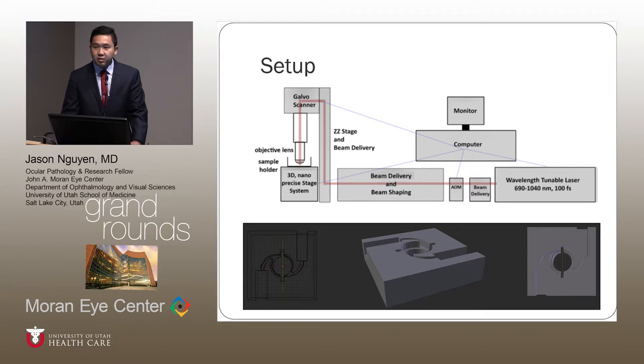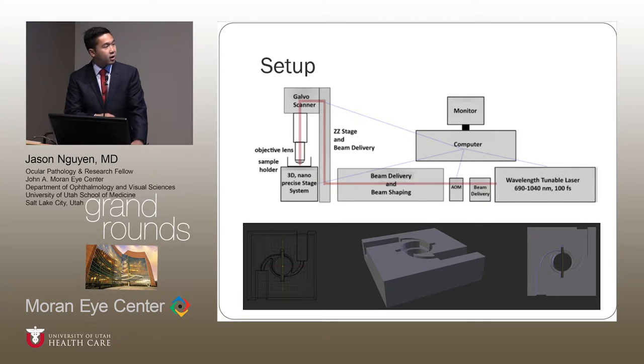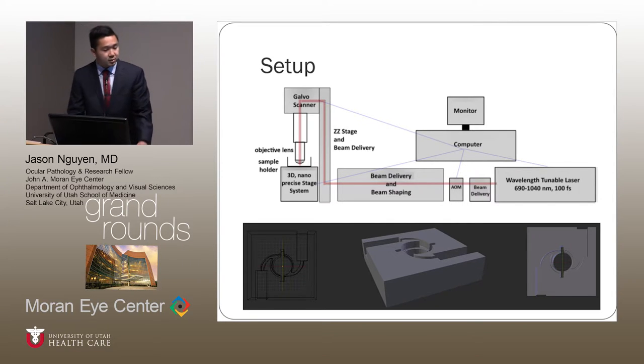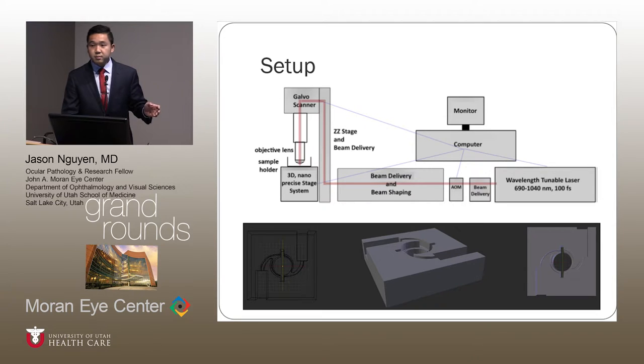The basic setup of the Perfect Lens Company: they start with the laser, it's delivered through and shaped to the galvanometer scanner. Through the galvanometer scanner, it goes through an objective lens to where the IOL sits. The bottom figure is an image of the IOL holder — it has to be immersed in water, because once the lens is treated, it has to absorb water to affect that refractive change. Otherwise, there really is no change at all.